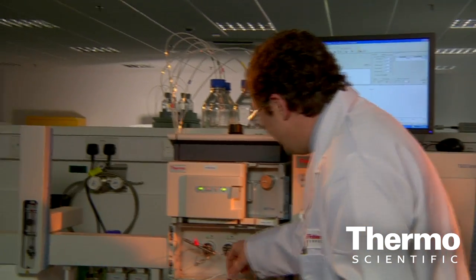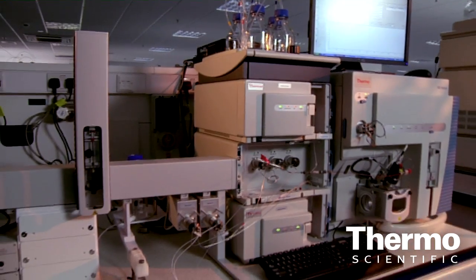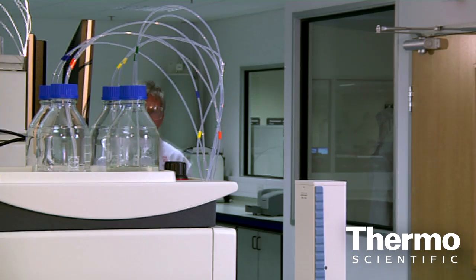And this here is the Thermo product that really does drive the productivity gains. What we've got here is an HPLC column which uses sub 2 micron particles. The advantage that has is it allows me to run very good separation, very efficient separations.